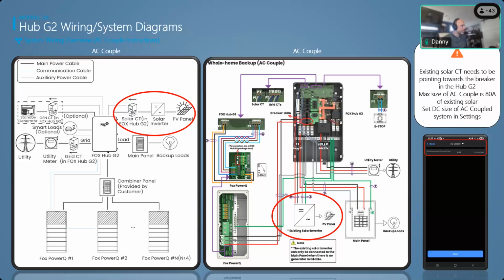String inverter or microinverters — yeah, so what's really nice about this product is not only can we do an AC connection or retrofit for anything pre-existing, but you can also add DC side too. Let's say they want to add more panels — you don't have to stick with a full AC system or add to that existing AC system. You can just add DC panels on top, run those right into there with the AC connection, and run all those in conjunction. So you can do both, which is a really neat feature for our product.